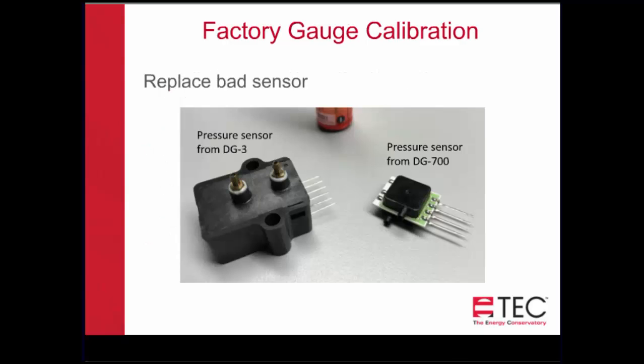So when we replace a bad sensor, you can see on the left-hand side the pressure sensor of the DG3, which is considerably larger than the pressure sensor of the DG700 on the right-hand side. You can see in the center towards the top, that is a AA battery, so that gives you an idea of the relative size that we're dealing with when we're talking about pressure sensors, both the DG3 and the DG700.